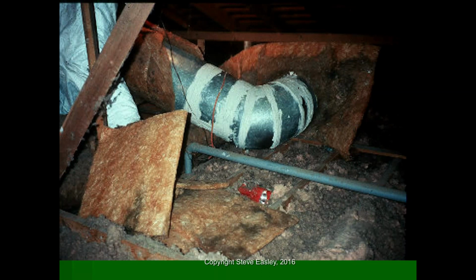So I would say, if I had to give you a number, probably when you start getting above 1,000 square feet, and again, layout has so much to do with this. I mean, mini splits in themselves, to more larger rooms, open spaces, you can get by with just one evaporator coil that can move enough air. It's a sizing issue.